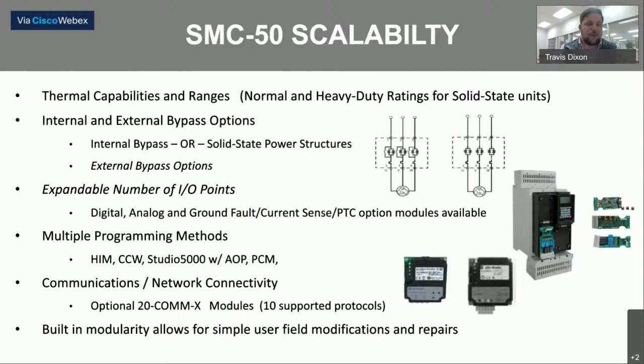Also, you can have up to 3 digital, analog, ground fault current sensing or PTC modules, and multiple programming methods via HIM, Connected Components Workbench, Studio 5000 with an AOP. It's also programmable by what's called a PCM card, which is a card for the SMC 50 that makes it dip switch configurable. And that built-in modularity allows for simple user field modifications, like the example I used for the SMC Flex. If you wanted to upgrade communications, it's very easily done in the field.